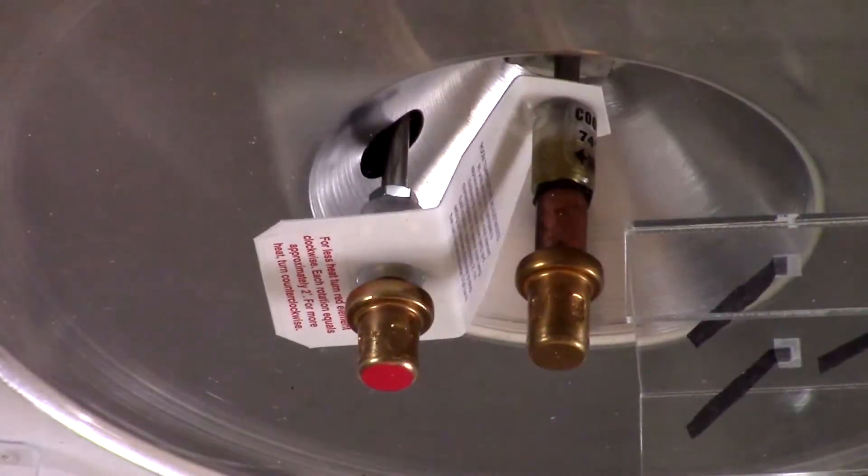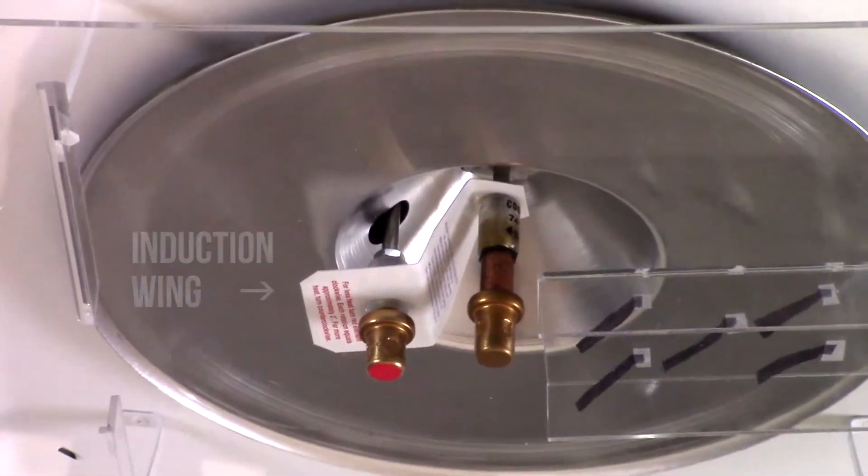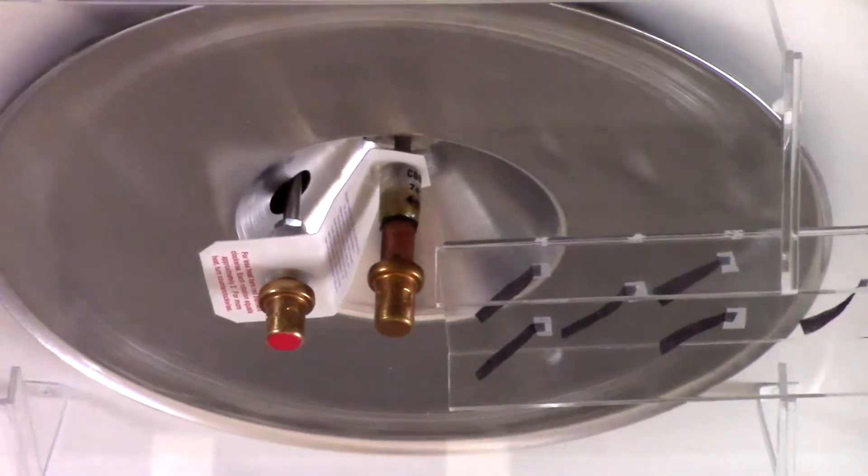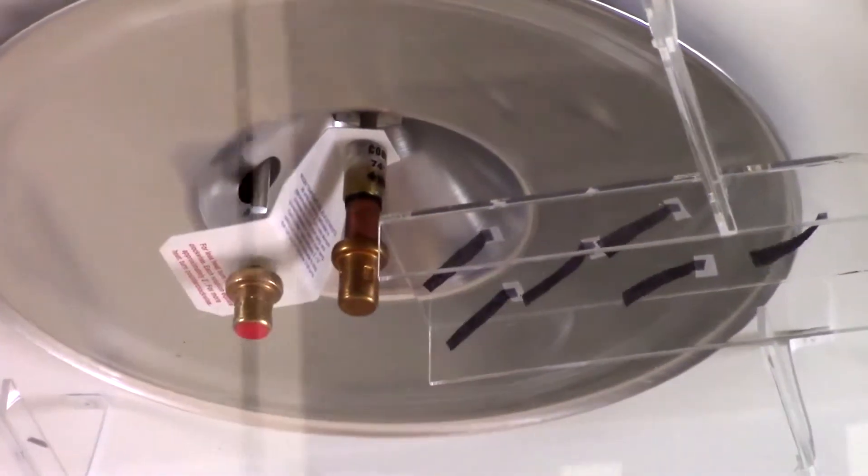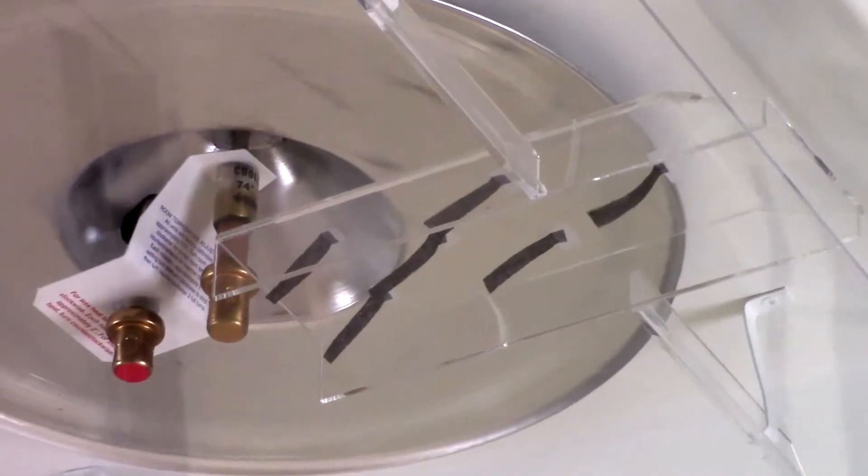Room air is induced over the thermal actuators by a simple yet highly effective induction wing. A small amount of supply air passes through a louver in the diffusion damper. This air is diverted off of the induction wing back into the supply air path.